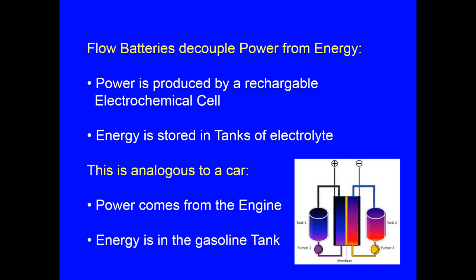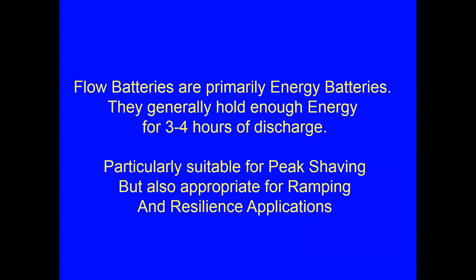If you want more power, you have more of these fuel cells in the middle. This is very analogous to a car where the power comes from the engine but the energy is in the gasoline tank. Flow batteries are primarily energy batteries — they generally hold enough energy for three to four hours of discharge. This is different from other batteries, which are basically power batteries. Because they can hold appreciable amounts of energy, they are particularly suitable for peak shaving, but also appropriate for ramping and resiliency applications.